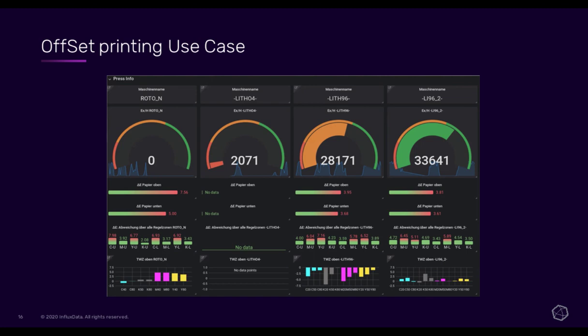An example was with these printers, you have the little jets that are using the various ink to print the images, and you need to do some cleaning of these things. And there was this story that they relied on that said every 6 hours you have to clean them. But it wasn't really based on any data. And the moment that they were able to start to collect the data, they understood that actually, the cleaning is going to be based on the type of materials that this thing is printing on. If they have something that maybe doesn't require as much consumption, maybe they don't have to do it every 6 hours. So they started to realize that by collecting that data, they could make decisions about the activity in the factory that were not based on folklore, and actually help them to make things a lot more efficient.